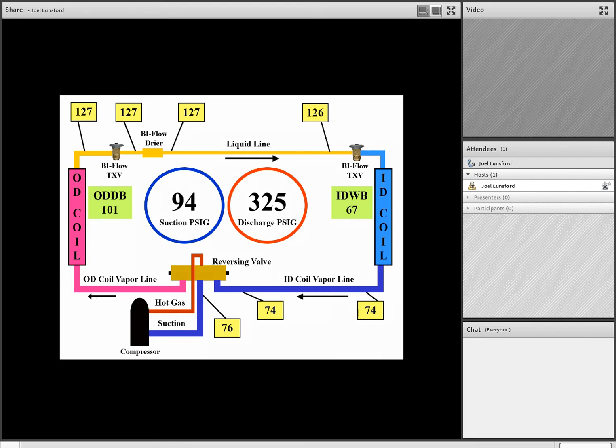At 325 pounds of pressure for R22, we see that we have a pressure temperature conversion of about 138. And the temperature leaving on the liquid line of the outdoor coil in the cooling mode is 127. So we have a subcooling level of 11 degrees. That's normal. So we have high superheat, about normal subcooling, high suction pressure, and high discharge pressure, or liquid pressure.